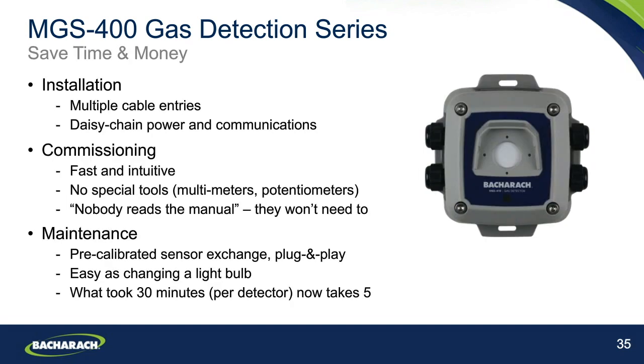A lot of the design here really has been focused upon how time and therefore money can be saved when using these systems. Installation is very simple. There are multiple cable entries within the enclosures, which allow for a very straightforward way to daisy chain the power and communications within the systems. And it's worth highlighting here that the MGS-400 platform has separate terminals for power going in and out of the system, and for the digital Modbus communications going in and out of the system. So it's very clean, very easy, and very straightforward to connect the wiring and install the system.